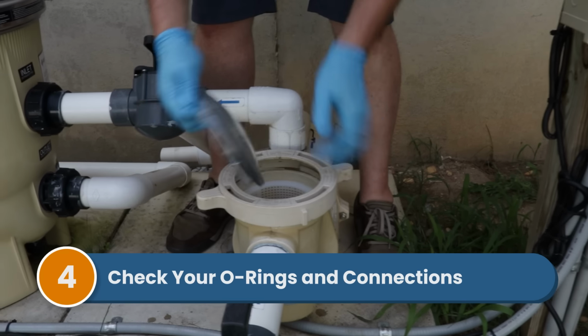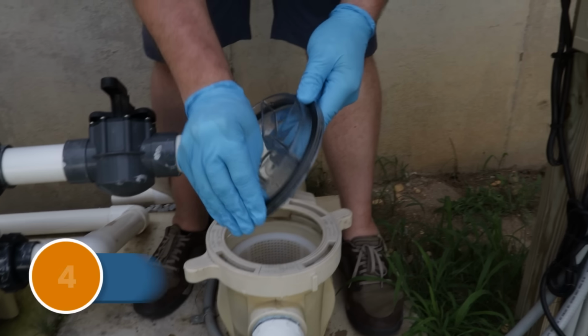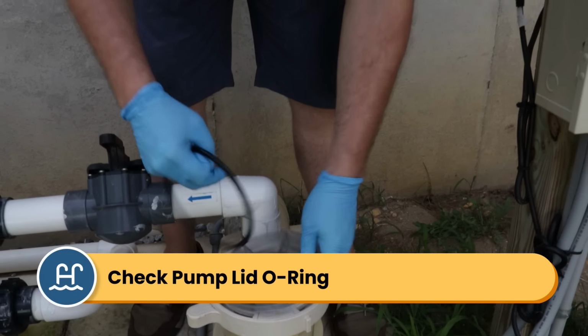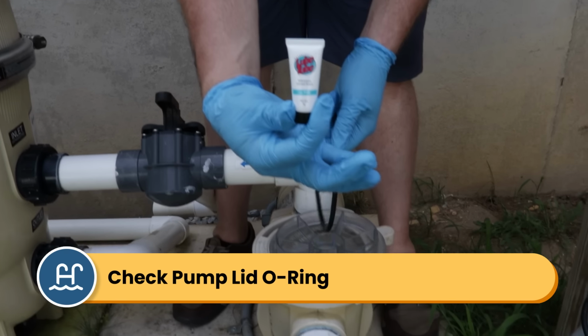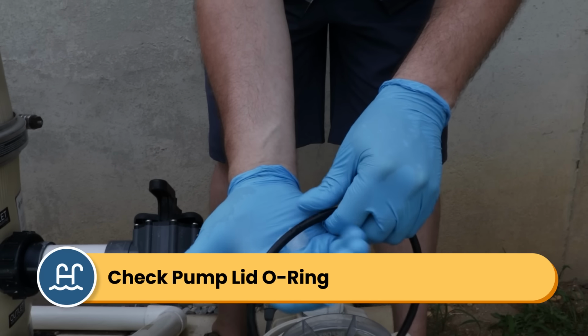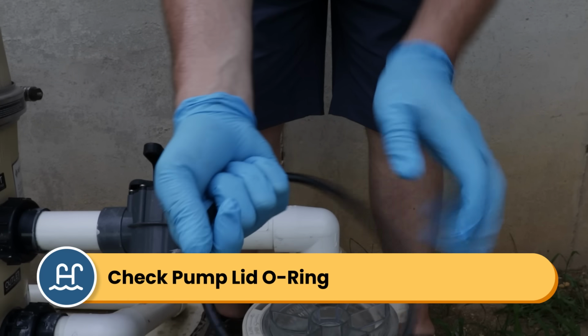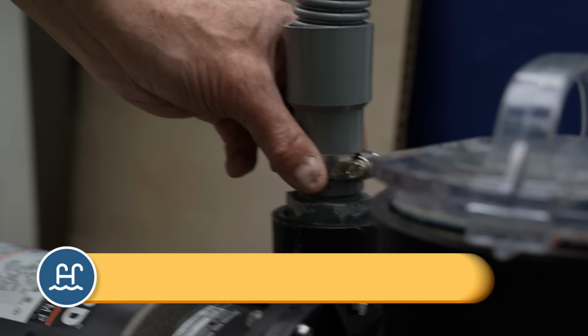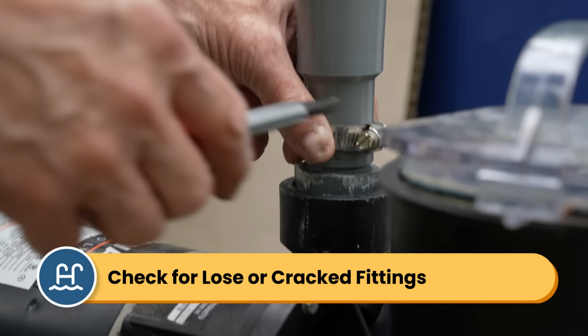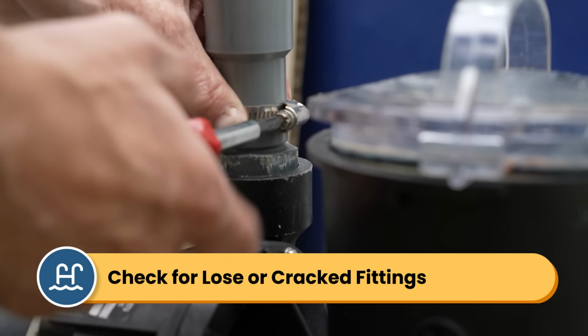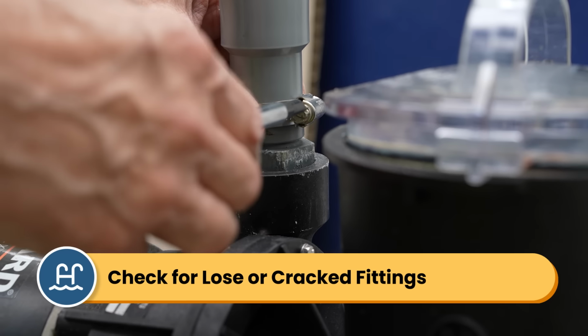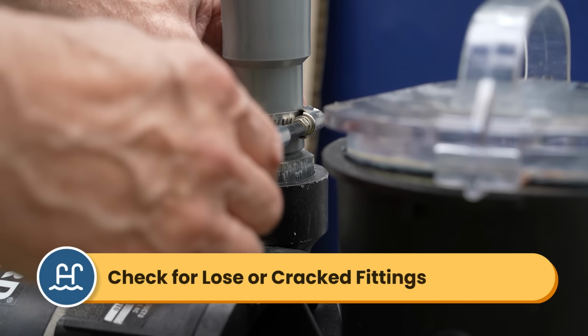Step number four is to check your O-rings and your connections. When O-rings crack or dry out, they let air in. So you want to check your pump lid O-ring for damage. Look for cracks by bending it with your fingers and adding some silicone lube, or replace it if it's too damaged. Loose pump connections can also let air in. So you want to check all of your unions and fittings around your pump and tighten any loose parts, or look for damp spots where water might be escaping.